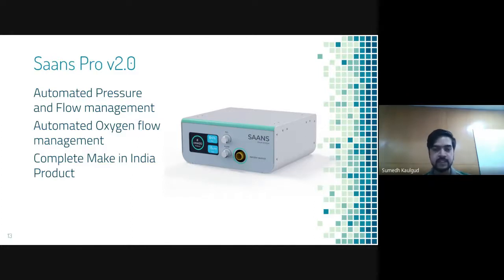One more advantage is that during the oxygen crisis, a lot of hospitals were receiving oxygen which was not of the required purity. Generally oxygen cylinders are 99% pure oxygen, but during the pandemic we saw places getting cylinders of 80%, 50%, 60% purity. In that scenario, using our oxygen sensor, we had developed a control system algorithm which ensured that the final oxygen concentration that reached the patient was the one that the doctor required. So no matter what the purity of the incoming oxygen is, the therapy delivered to the patient is always accurate.